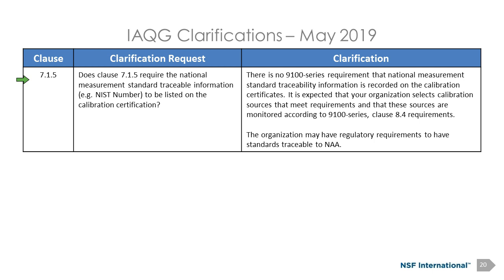It's expected that your organization selects calibration sources that meet the requirements, and that these sources are monitored according to your supplier quality requirements or your external provider requirements. There may also be some regulatory requirements that you have to adhere to, some National Aviation Authority requirements, as it says down here. But overall, there isn't a direct requirement that says the certificate from your external provider needs to link to the NIST number or the traceability number for NIST. Now with that, we do need some evidence to show what standards were used on the certificate. So the serial numbers, but as far as linking to the NIST number for the serial numbers that were utilized, that can be done in other records. Hopefully that makes sense.